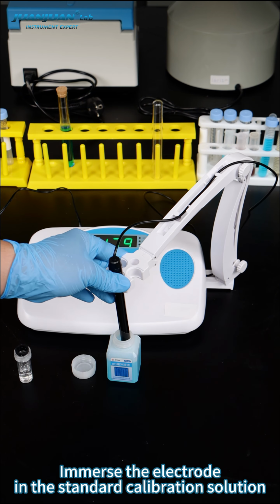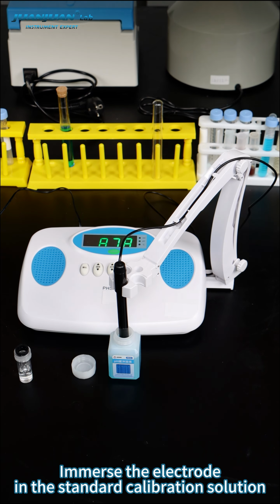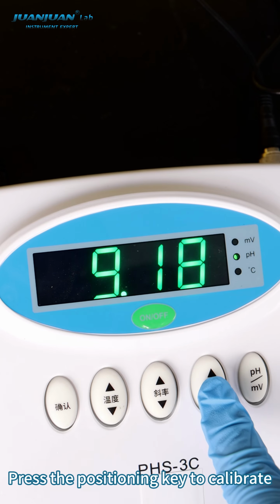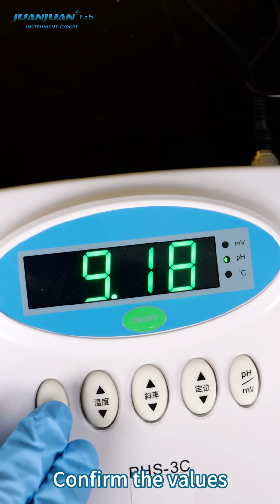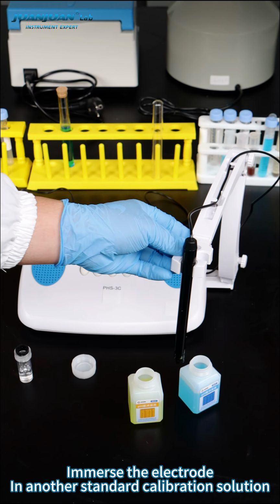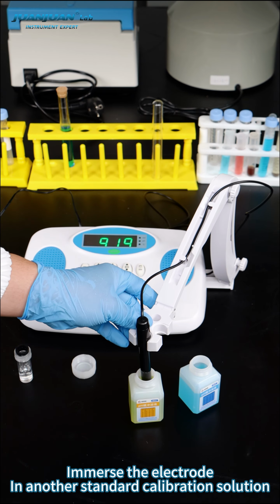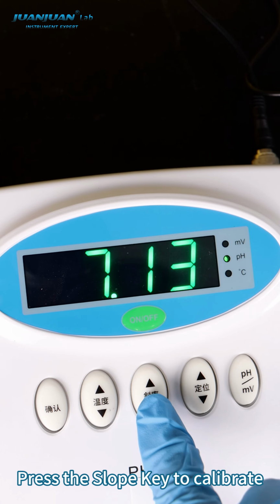Immerse the electrode in the standard calibration solution. Press the positioning key to calibrate. Confirm the values. Immerse the electrode in another standard calibration solution. Press the slope key to calibrate.